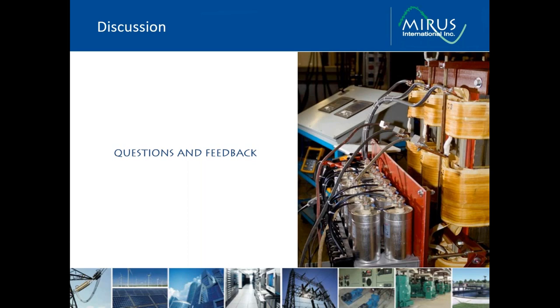And they're asking, is there any safe switching frequency? For example, this cited above 20 kilohertz. Would that be considered a safe switching frequency? Yeah, certainly the higher the switching frequency of the IGBT, the easier it is to filter that frequency. And if it is filtered well, then that will be a better solution than the lower switching frequencies that are much more difficult to filter effectively. And most manufacturers will then cut corners on the filters, and that's why we start to see these IGBT switching frequencies on our power systems. So yes, if the IGBTs can be switched at a faster or higher switching frequency, you will reduce this effect.